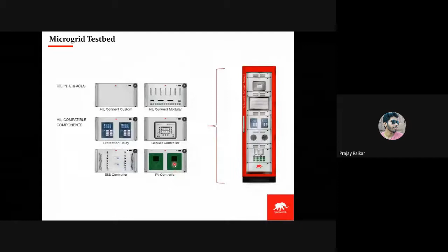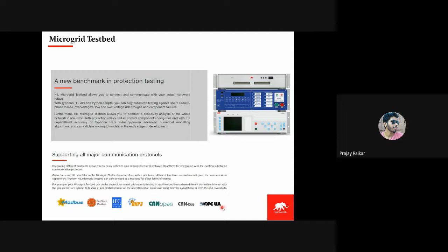This setup can help you test your protection scheme along with the communication protocol, so all the latency of the communication protocol can be counted. It offers different communication protocols, and the same applies to battery energy storage, where you can test your battery energy storage converter with protocols like Modbus, Sunspec Modbus, IEC 61850, DNP3, CANopen, CAN Bus, OPC UA, Ethernet, and so on.